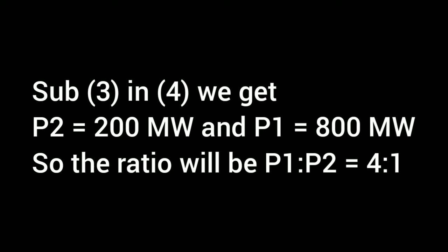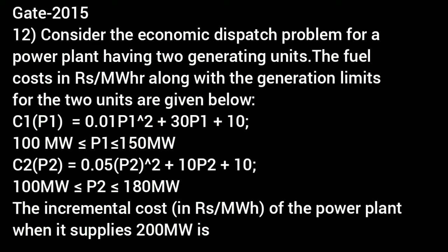This question was asked in GATE 2015. Consider the economic dispatch problem for a power plant having two generating units. The fuel cost in rupees per megawatt hour along with the generation limits for the two units are given below. C1 of P1 is equal to 0.01 P1 square plus 30 P1 plus 10. The limits are 100 megawatt less than or equal to P1 less than or equal to 150 megawatt. C2 of P2 is equal to 0.05 P2 square plus 10 P2 plus 10. Its limits are 100 megawatt less than or equal to P2 less than or equal to 180 megawatt. The incremental cost in rupees per megawatt hour of the power plant when it supplies 200 megawatt is.